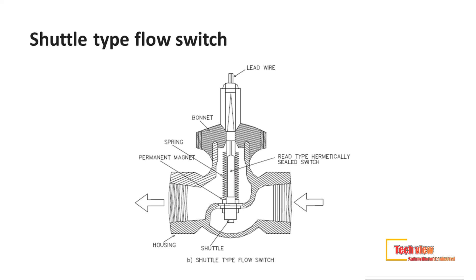The shuttle is displaced as the liquid flow increases to the actuation area. This shuttle operates the reed switch inside the unit stem. When displaced by fluid flow, the shuttle returns when the flow decreases and sits on the port seat.